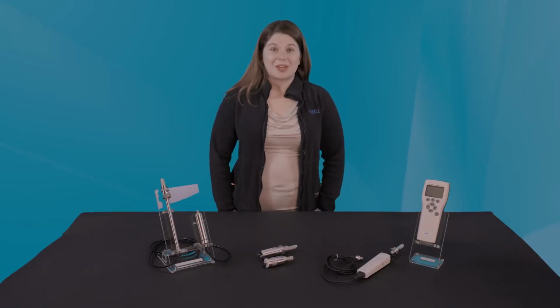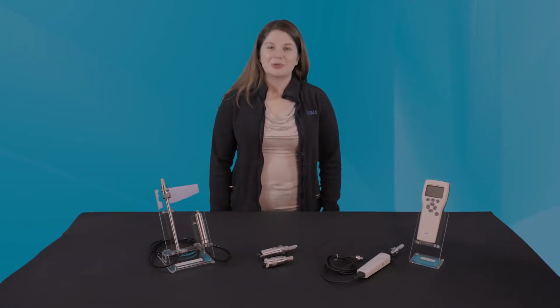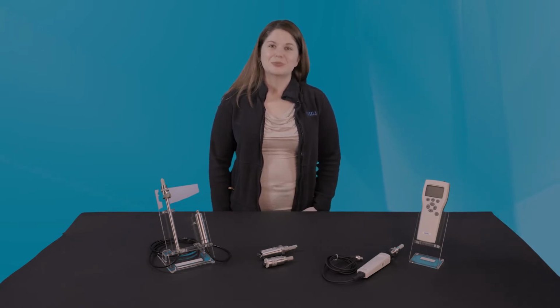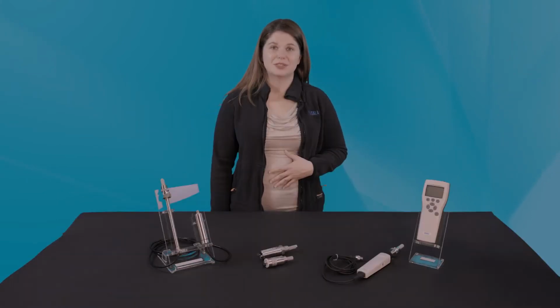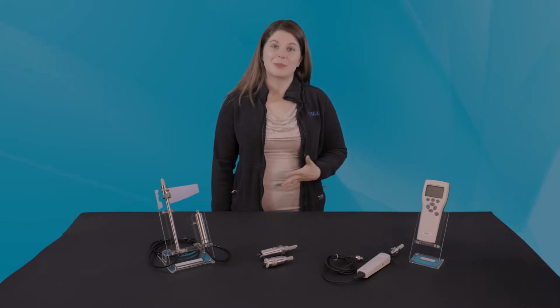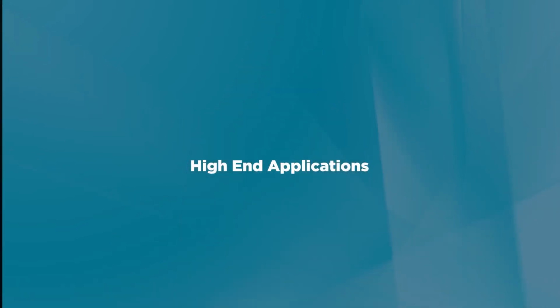Now that we've covered compressed air, let's talk about solutions for other dew point applications. Lithium battery and plastics drying applications often require extremely dry air to ensure product quality. Our DMT-152 low dew point transmitter is a compact, accurate, and robust solution still based on our DRYCAP capacitive polymer technology. The DMT-152 offers our driest available measuring range with a calibrated range down to -80°C, as mentioned before, and a full measuring range down to -100°C dew point.